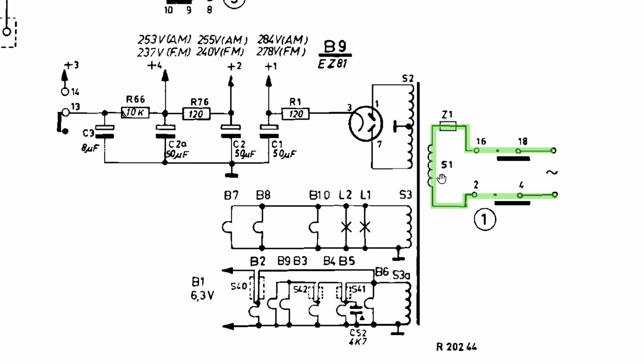Now, I know this isn't complete because we've got a voltage selector. The voltage selector works by choosing where on this winding you feed in your supply. If it's a high voltage like 245, it'll be at the top end, and if it's a lower voltage, it'll be at different taps down the bottom, okay?